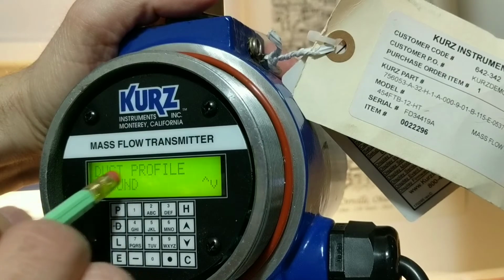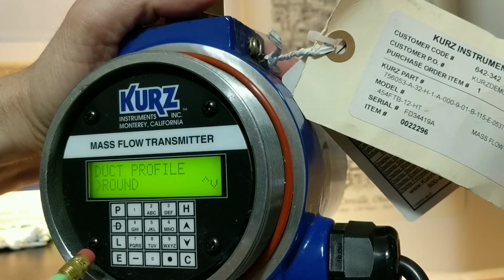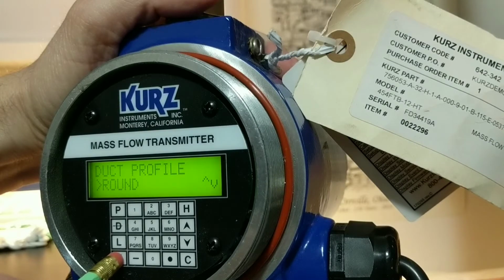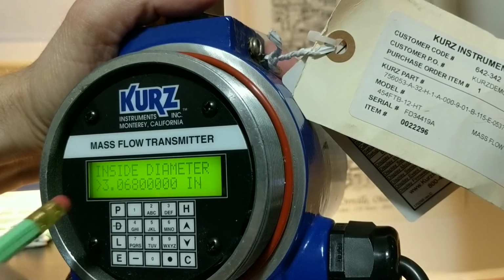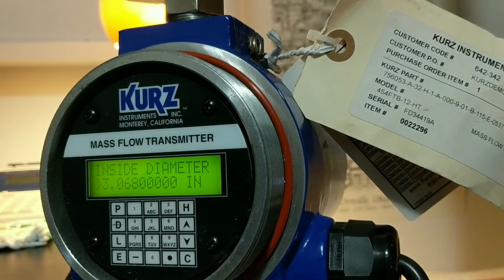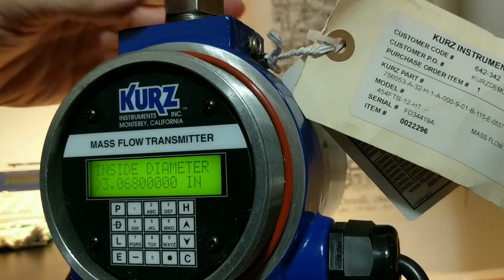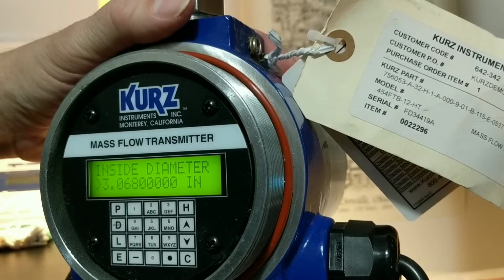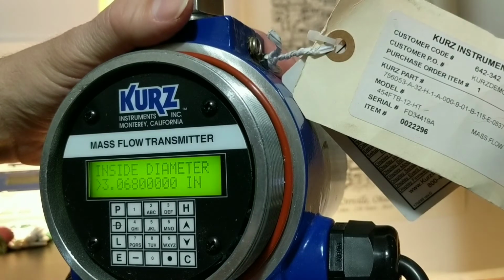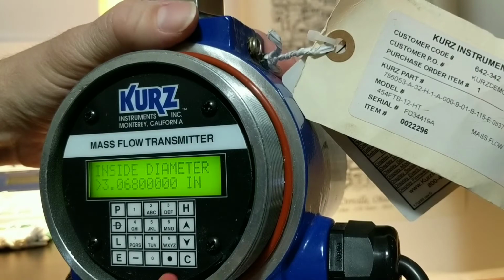Make sure that your duct profile is round, basically saying you're going through a round pipe rather than a square duct. I believe yours is set properly there. If it's not, you'll need to go up or down to change that. We're going to hit enter. And then the first thing that you're going to need to change, I can't remember what yours was set to, but now that we know that you have a Schedule 40 6-inch pipe, we're going to need to make sure that the inside diameter matches the 6-inch pipe. And the inside diameter should be 6.065 inches.